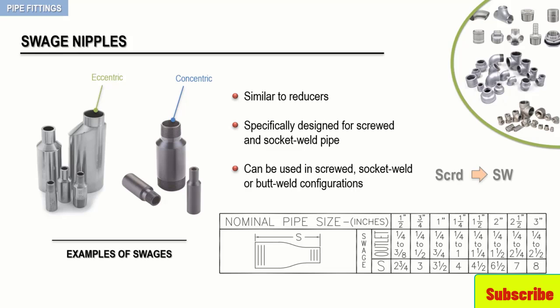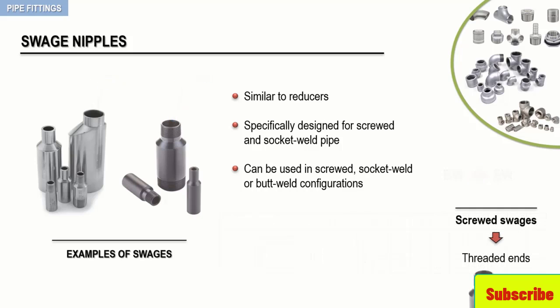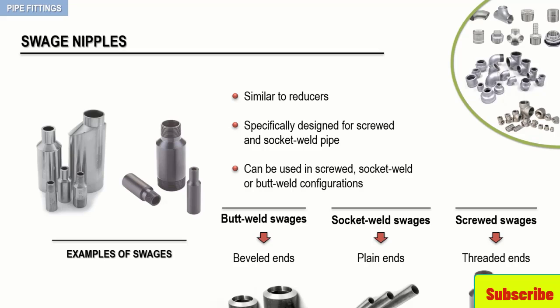The possible configurations are: screwed to socket weld, butt weld to screwed, or butt weld to socket weld. Screwed swages will have threaded ends, socket weld swages will have plain ends, and butt weld swages will have beveled ends.